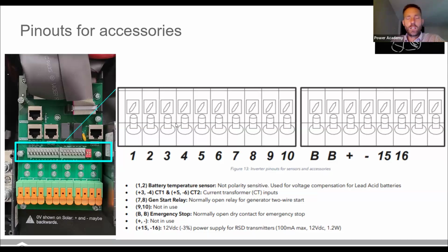CTs: even though a Sol-Ark 15K has 200 amps of pass-through and all that power from the utilities coming through it, Sol-Ark still recommends that you use your CTs. So 3 and 4 would be leg 1, 5 and 6, leg 2. The auto start we just talked about, pins 7 and 8. Not using 9 and 10, but B and B is your e-stop button, and that's a normally open dry contact. If you short pins B and B out, that will shut down the loads and the entire inverter, so that would be for your rapid shutdown. Pins 15 and 16: if you do use an AP Smart transmitter, you could actually power it off pins 15 and 16 for the rapid shutdown.